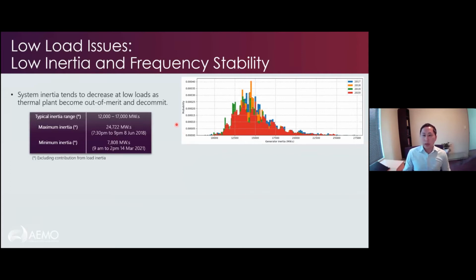So the second issue is relating to low inertia and frequency stability. System inertia tends to decrease at low loads, because synchronous plants are decommitting as they come out of merit. You can see here a histogram of the inertia ranges between 2017 and 2020. The typical inertia range is in that 12,000 to 17,000. I should say this is all just generator inertia, so we're excluding the load side inertia, but that would be fairly proportional to the generator side inertia.